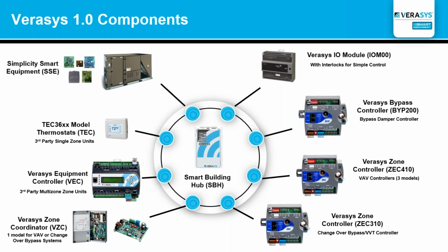The reason I say that is because there are so many different configurations of VAV. You could have a series type of fan, you could have parallel, you could have dual duct, you could have all kinds of different VAV applications. What we've done here is we have 3 models of our VAV controllers, and that is it. It's based on heat. If you want a VAV controller that does electric heat, you would order that one model. If you want hot water, you would order the second model. If you want SCR, proportional, you would order the third model.